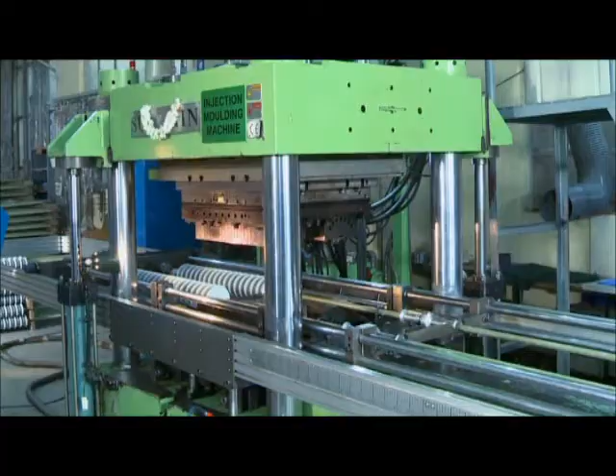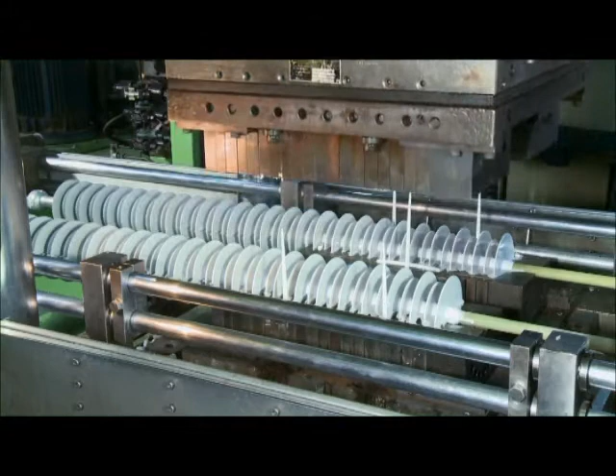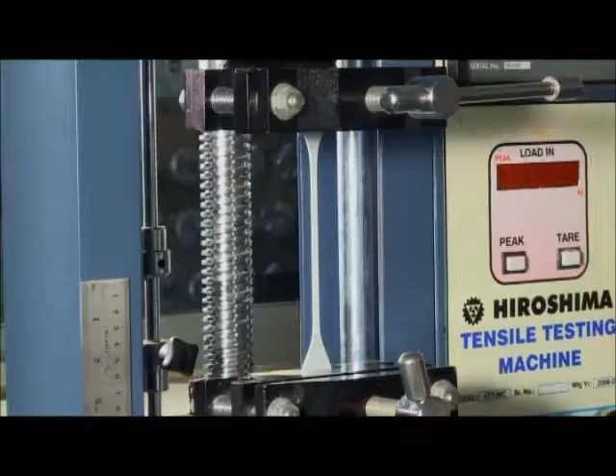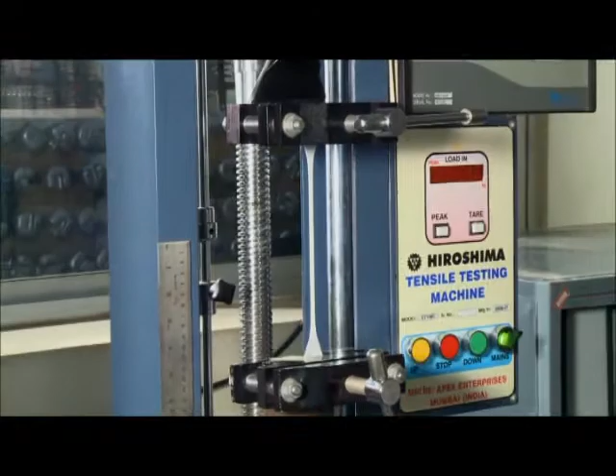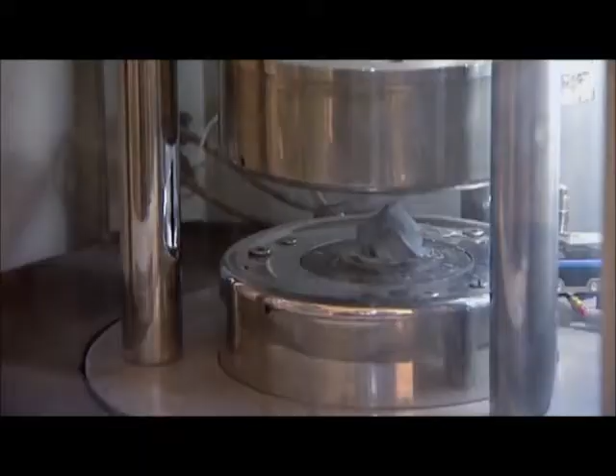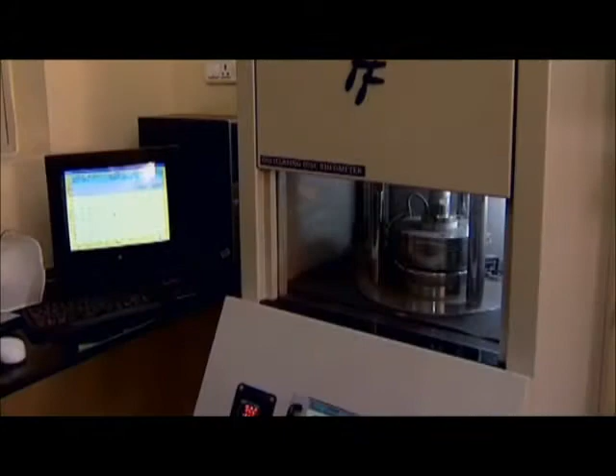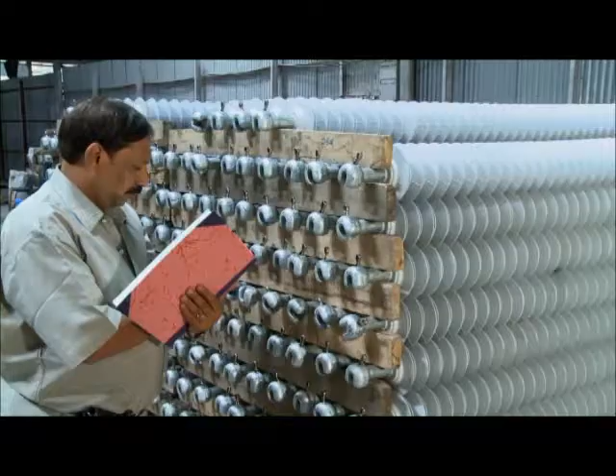The fiber-reinforced rod is fixed with the metal fittings in crimping machines. The silicone used to form the sheds is injected through an accurately controlled system to form the shell. The mold used is engineered to suit the profile and meet the system requirements. A sophisticated laboratory ensures the quality checks on the process. The composite insulators undergo rigorous electrical and mechanical performance tests for qualification.